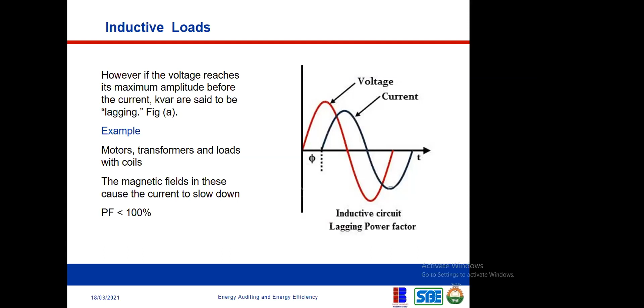When you have something like this, kVAR, which is wasted electricity, is induced in the system. Examples of such loads are motors, transformers, and loads with coils. All loads with coils actually induce kVAR into your system, displacing current and voltage, putting them out of phase, and wasting electricity. The magnetic field causes the current to slow down, so you cannot have a power factor of 100%, it will always be less than 100%. So these are inductive loads, your motor systems, transformers, and all of that, and they affect your power factor. Next, please.